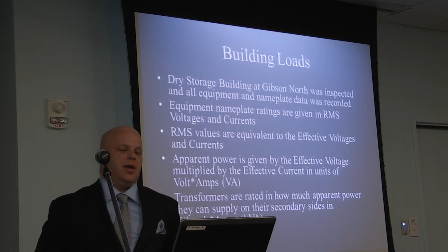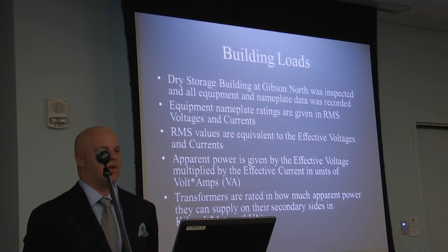The dry storage building at Gibson North was inspected, and all the nameplate data for all the equipment inside was recorded. The equipment nameplate ratings are given in RMS voltages and currents. RMS values are equivalent to the effective voltages and currents. Apparent power is given by the effective voltage multiplied by the effective current in units of volt-amps. Transformers are rated in how much apparent power they can supply on their secondary sides in kilovolt-amps, kVA.